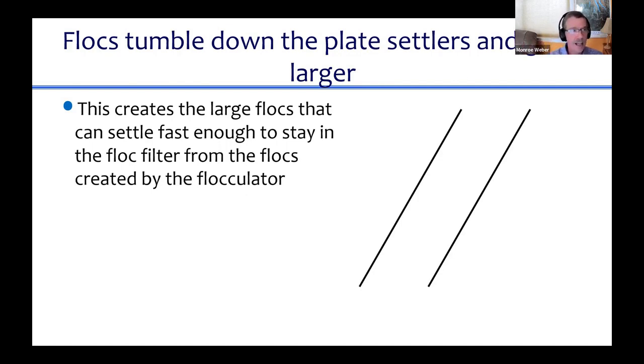Most water treatment plants have plate settlers. And the design for them is actually very simple. You say, we designed this plate settler and the flocks get captured in the plate settler, and then they're removed from the bottom of the sedimentation tank. But people forget this one little piece, because in between the plate settler capturing them and their removal from the bottom of the sedimentation tank, you're assuming that these flocks have the ability to travel down through the sedimentation tank.